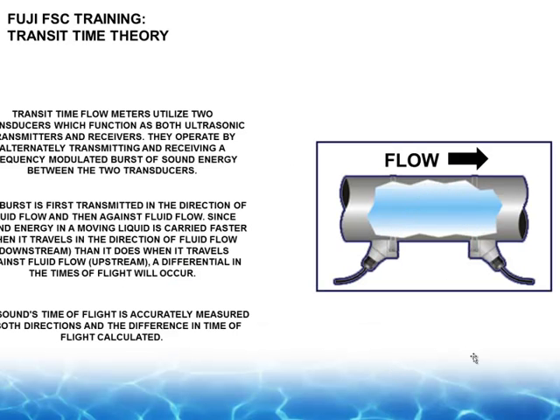Here I have a picture, a bird's eye view of a pipe. We got lazy. Instead of the man in the rowboat going across, he bounces off the back wall and comes to the same side. And the reason why, we're lazy. It's easier to put two sensors on the same side of the pipe. Flow is going from left to right. This sensor is going to transmit a sound burst across the pipe, ricochet off the back wall, and come downstream, and we measure how long it took to get there.